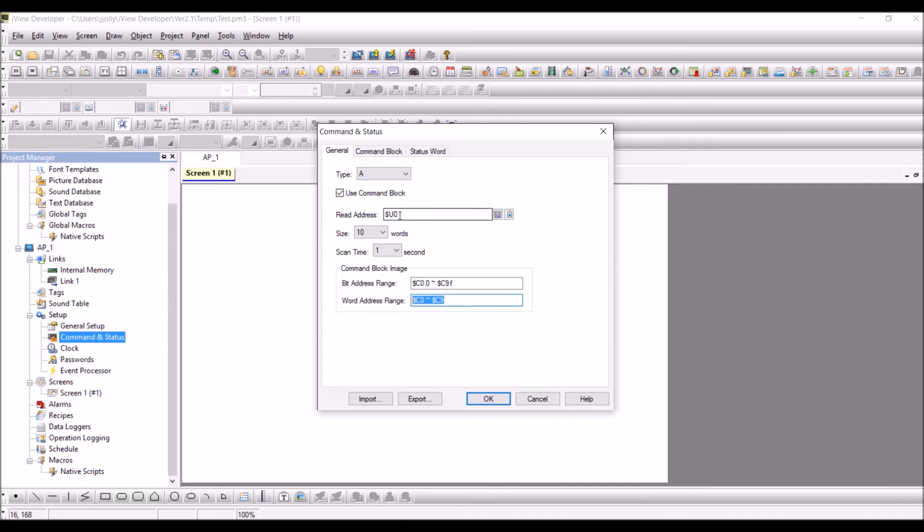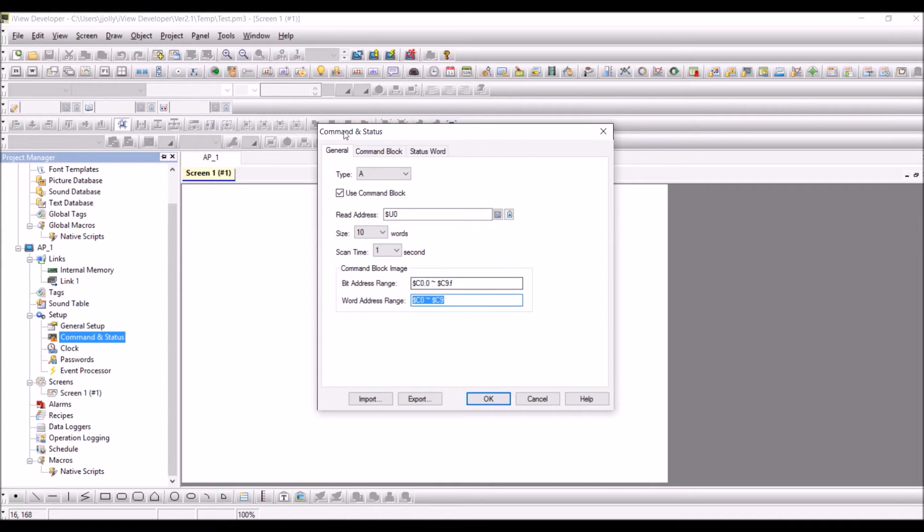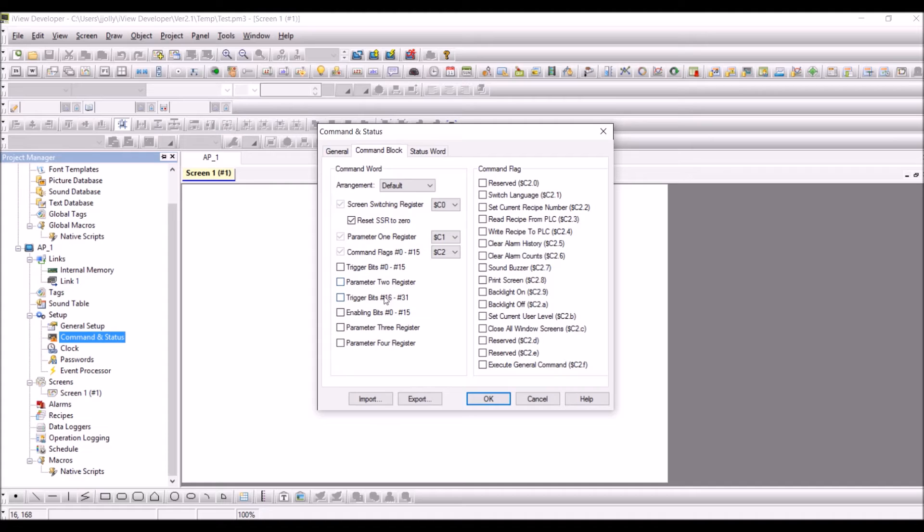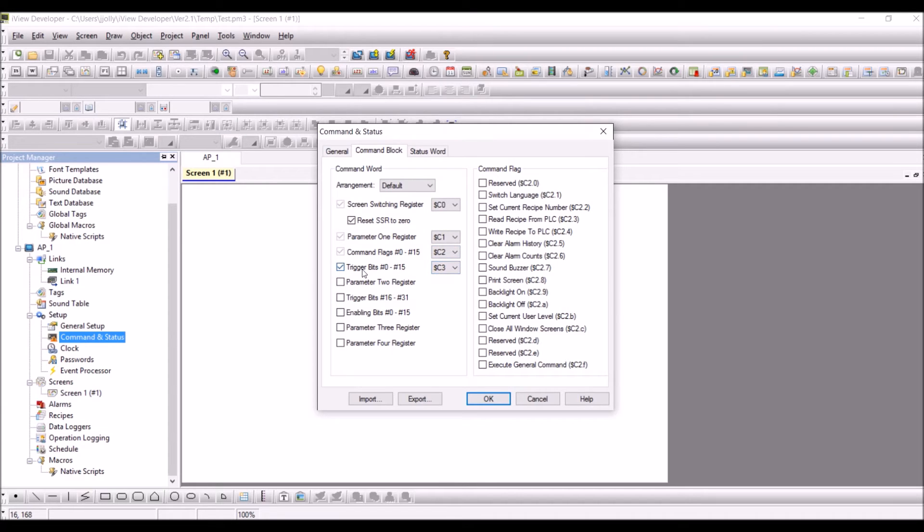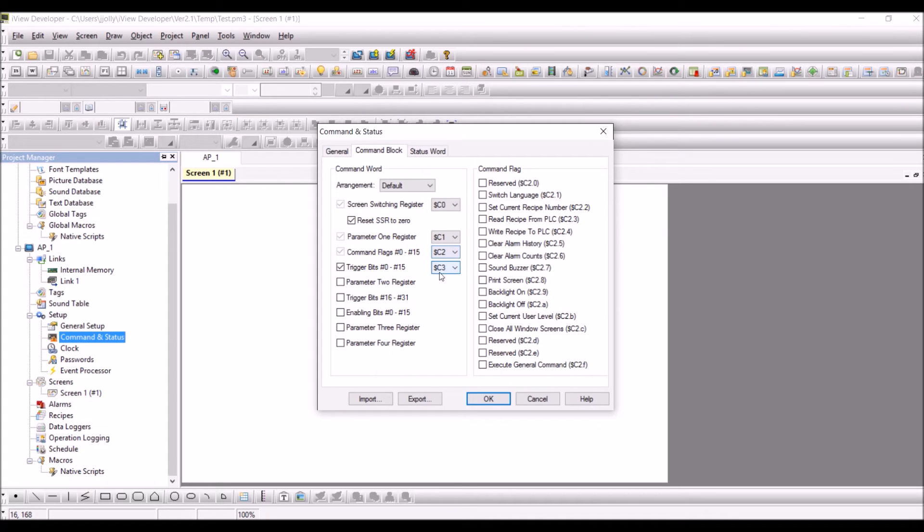So you do have command block so U0 is linked to C0, U1 will be C1 and U9 will be C9. So if we come back here we can look at this screen switching register will be C0 which is U0. Say for example command flags is C2 and if we tick this one this is C3. So trigger bits 0 to 15 is taking the value of C3 or the register C3 which means it is taking the dollar U3 value from here.